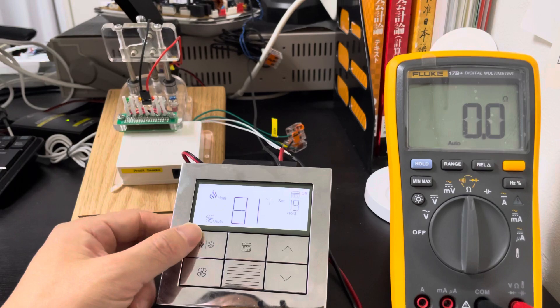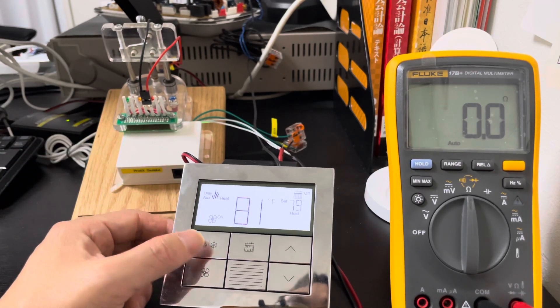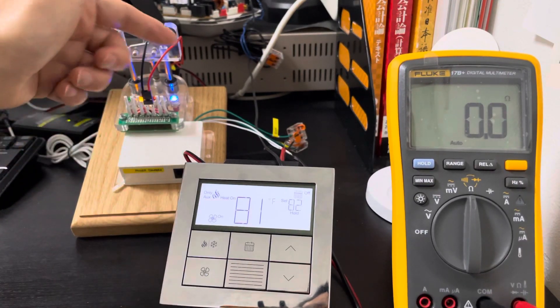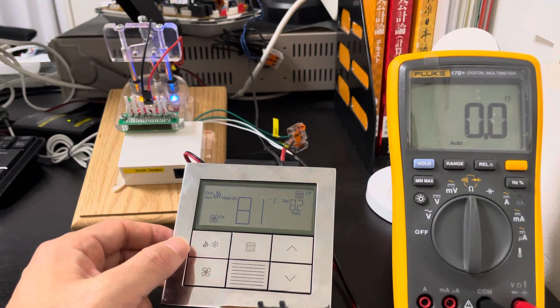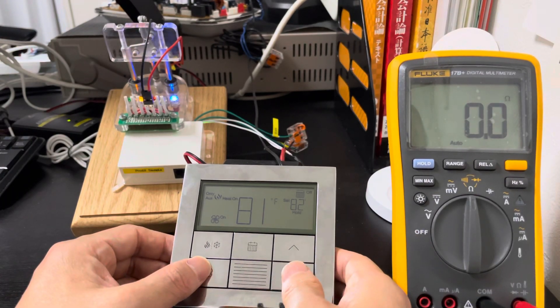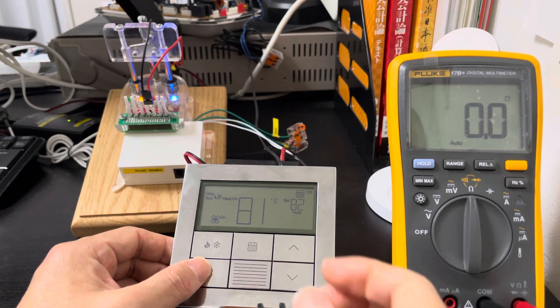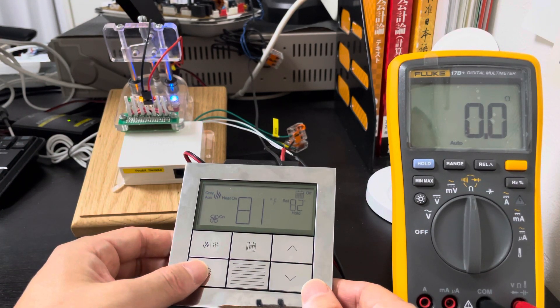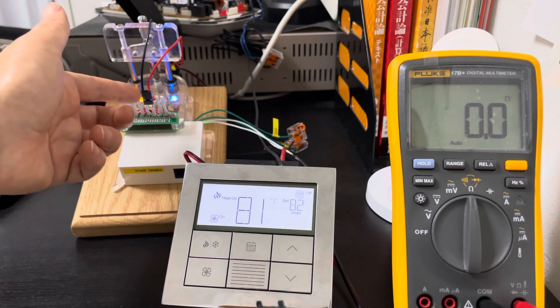We can adjust the touch temperature down and the in-floor system will turn off. We can also use FCU heat separately — adjust the temperature up and we can see the FCU heat is on. We can also use the in-floor heat as the main heat source and FCU heat as a temporary heat. When the FCU heat is on, we change the mode to in-floor heat and we can see the in-floor heat is on.